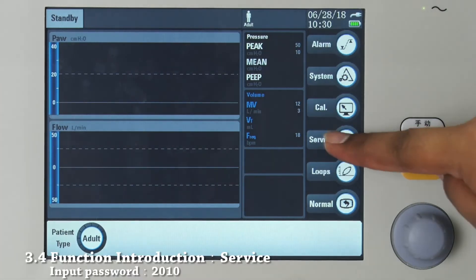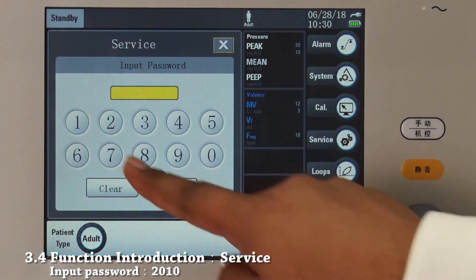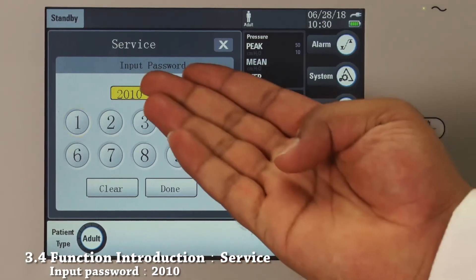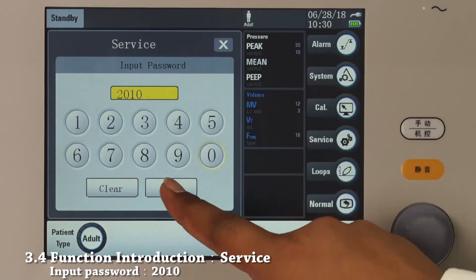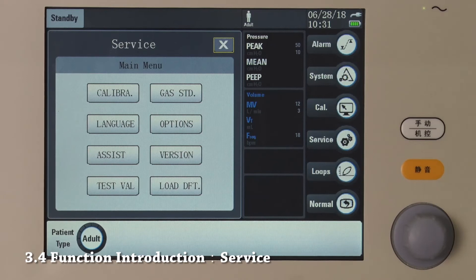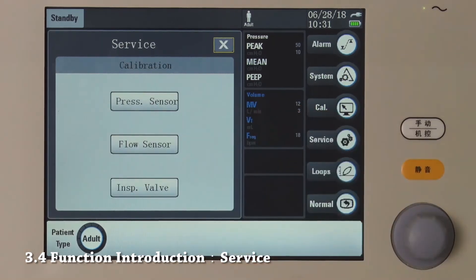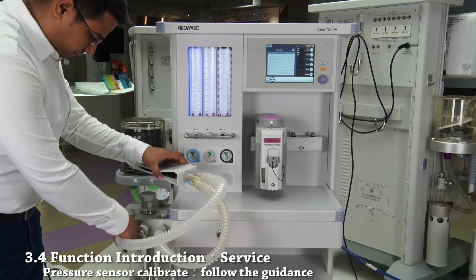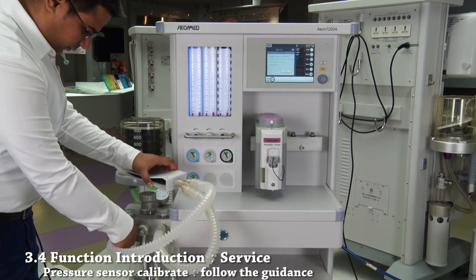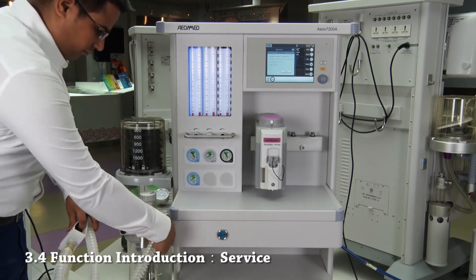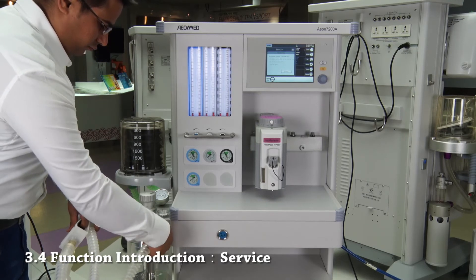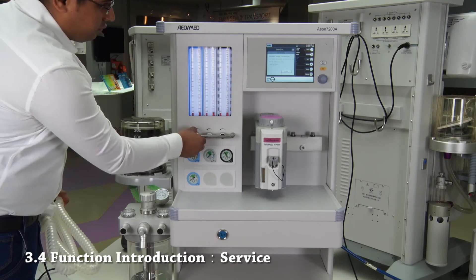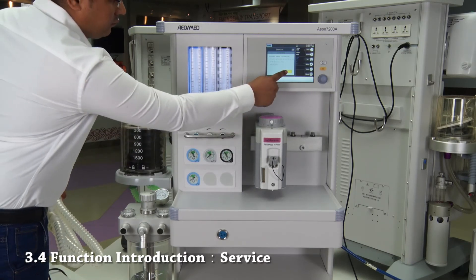This is the service tab. To get access, you need to enter the password — the password is 2-0-1-0. Press done to confirm. Enter the service calibration and between pressure sensor, flow sensor, or inspiratory valve, choose pressure sensor. For pressure sensor calibration, follow the instructions displayed on the screen. First, disconnect any hoses from the inspiratory and expiratory ports. Set all flow meters to 0 liters per minute and press start.